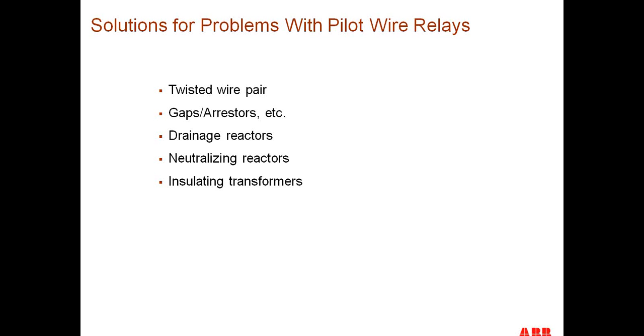So it's limited to less than 2 miles. So historically, when the new generation of current differential relays came out, people had in their mindset that same idea that we have to limit the use of current differential relays to less than 2 miles long. But in actuality, with the new types of communications equipment we have, you can run current differential relays upwards of 200 kilometers without any problem at all.